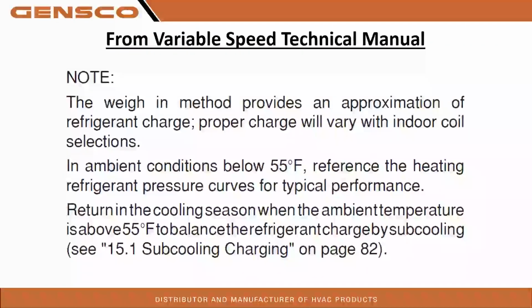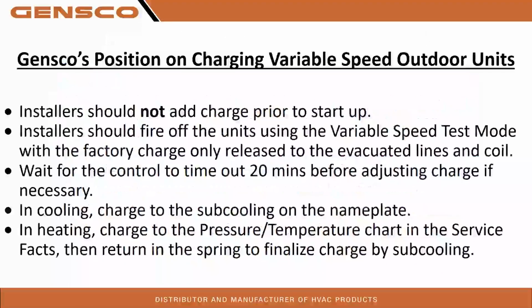And why we do not recommend that, I have it on the next slide. Installers should not add charge prior to startup. Installers should fire off the units using the variable speed test mode with the factory charge only released to evacuated lines and coil. So what we're going to do is we're not going to do the line set adder.